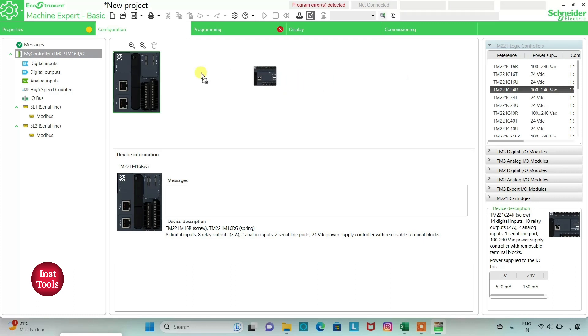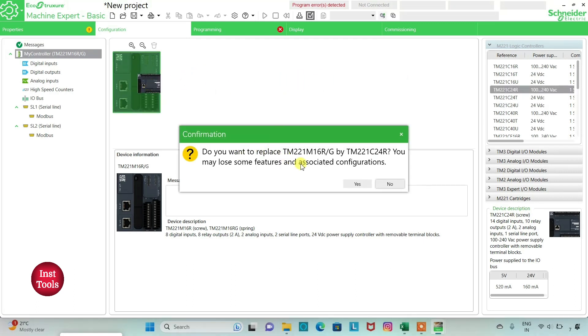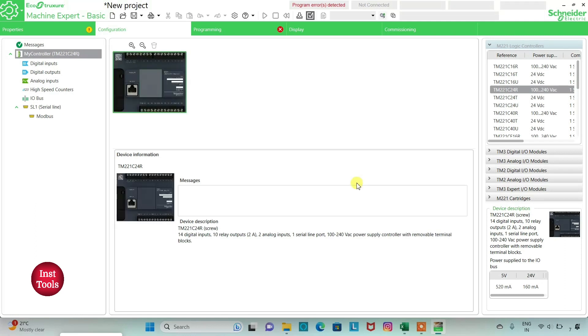Here is a list of different logic controllers with different configurations. I will be using the TM221C24R. I'll click on it and drag it in, then click yes to replace. This controller has 14 digital inputs, 10 relay outputs, 2 analog inputs, 1 serial line, and a 100 to 240 volt AC power supply with removable terminal blocks.